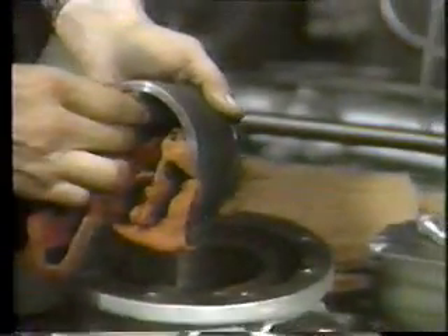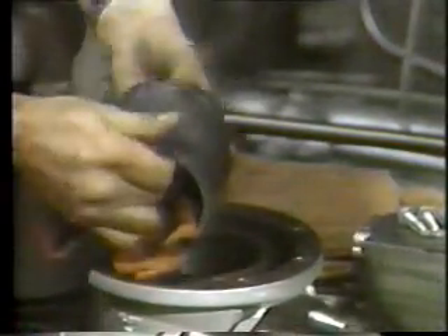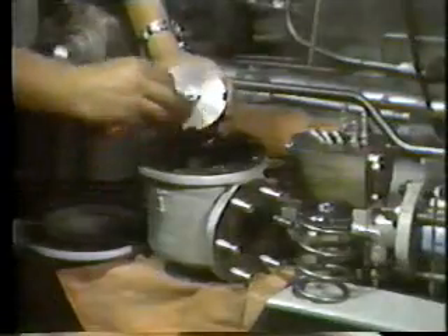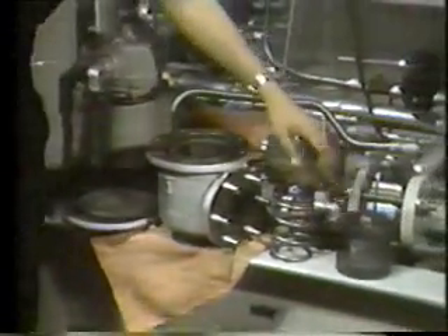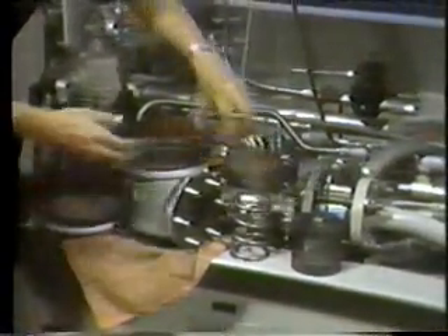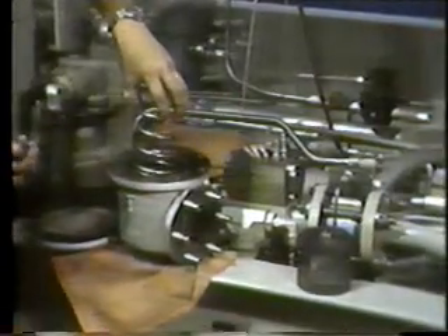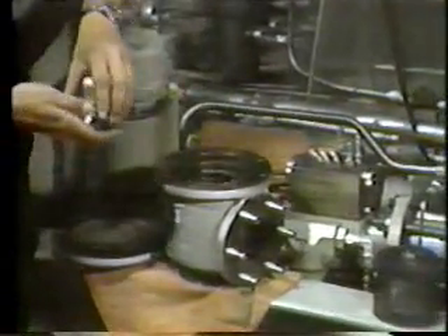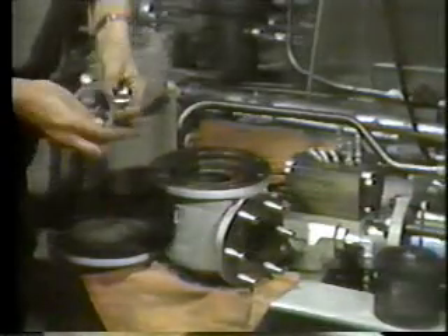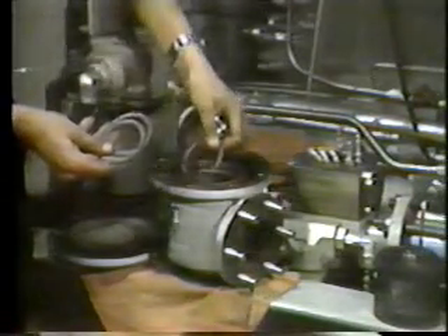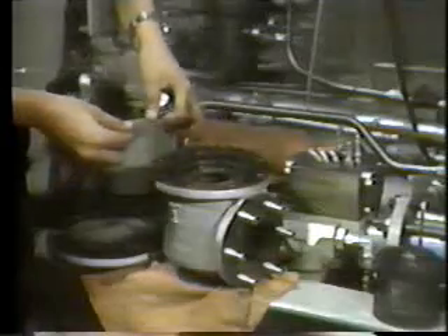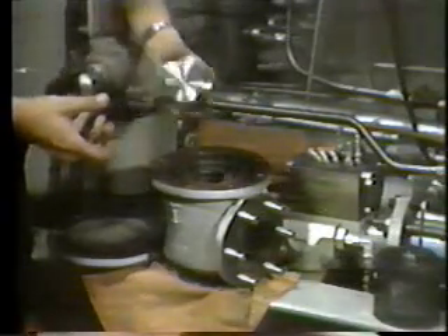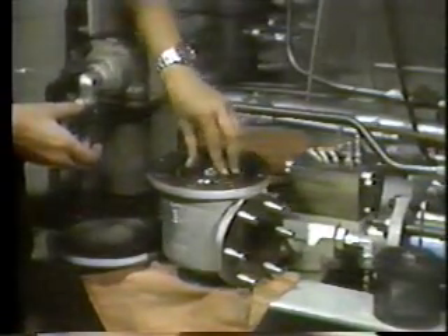Next, clean the components with a lint-free cloth dampened in Stoddard solvent. If any parts are found to be defective, replace the valve. Now install the spring. Next, install the correct amount of shims. Then install the spring seat. Install the piston.